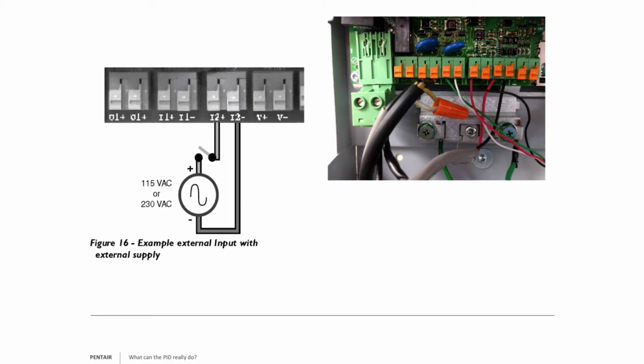So we're going to hook up to input 2 now using 115 and a float switch. And what you see there is input 2 coming out, and say for example it's the black wire, the float switch. Then in the float switch we have the white wire, which then I would connect to the white wire of, say, a 115 pigtail cord, and then I would connect the black of the pigtail cord into input 2 positive to complete the circuit. Now in the down position with the normally open, it will not pass voltage. When I lift the float, the point should close, and then voltage should be applied to input 2, which we would then program to run.